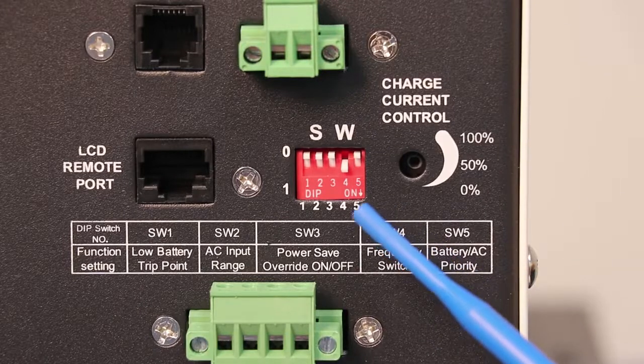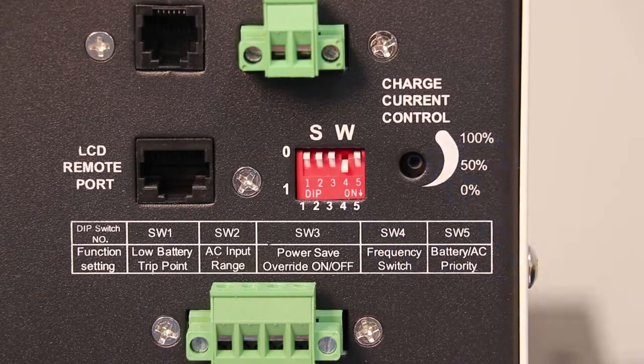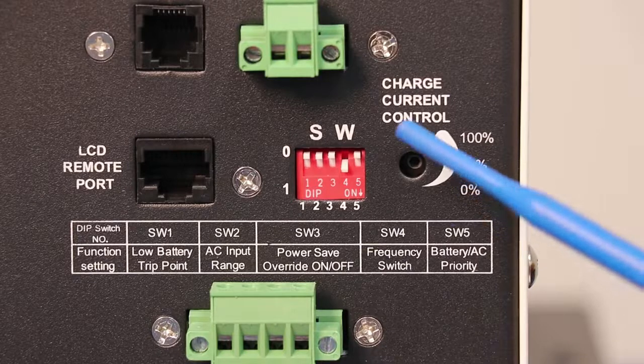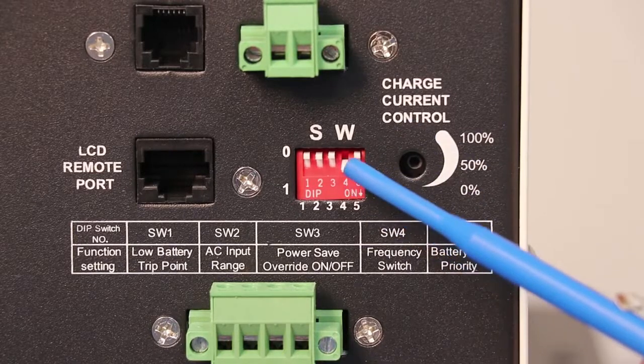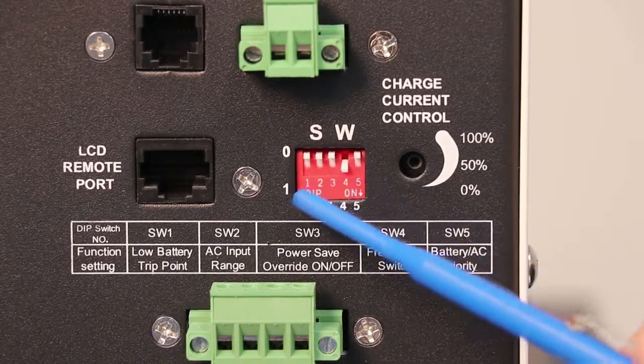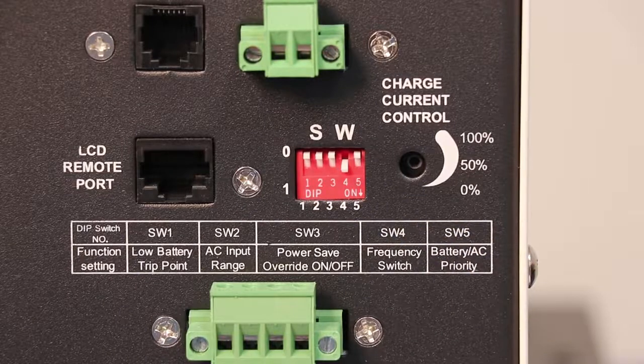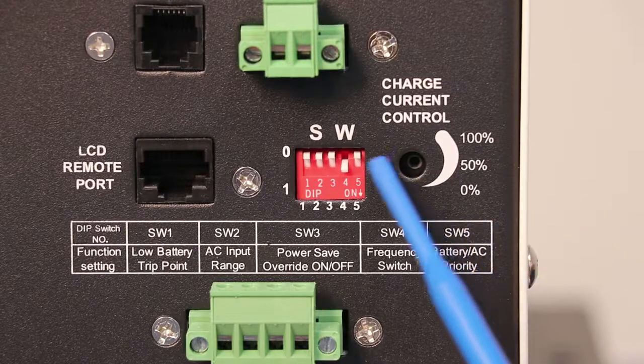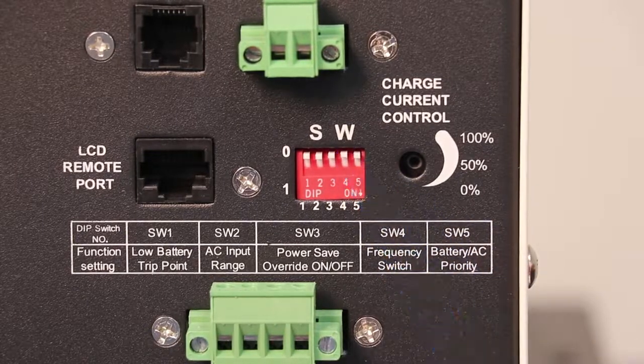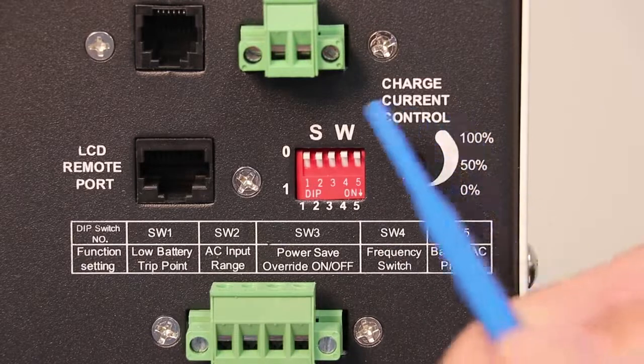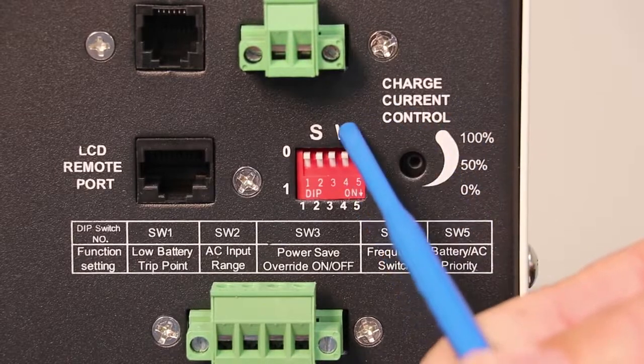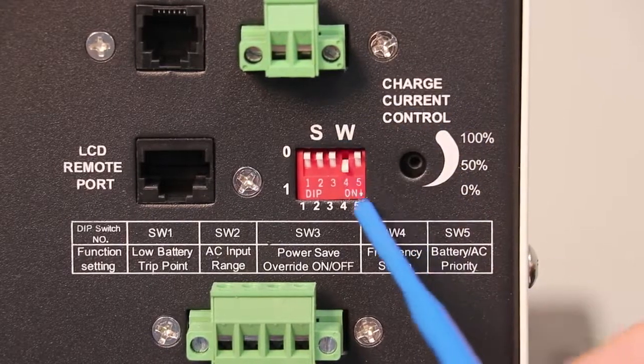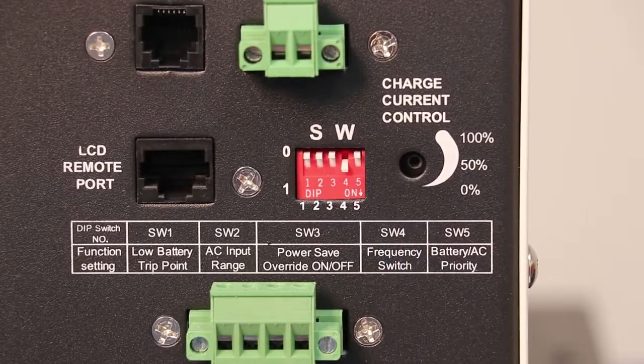I'm going to talk about switch position number 4, which is very important. In the position it's in now, position 4 is on, meaning the unit is set up for 60 hertz. If this was installed overseas, it would be set for 50 hertz. So you want to keep switch position 4 in the on position—that means this inverter charger is set up for the US and 60 hertz.